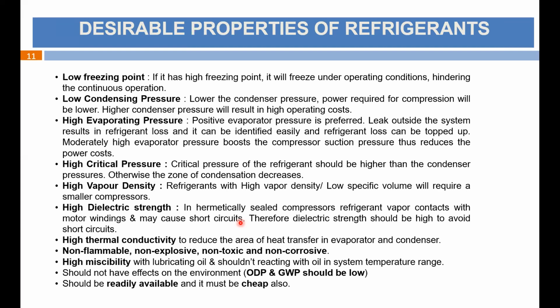And some refrigerants, as you know, operate at negative pressure, like R123. So positive evaporating pressure is preferred. If it is a negative pressure and any leak happens, then instead of refrigerant going out, the outside contaminated air gets in and the entire system gets contaminated. So there should be positive evaporating pressure. Moderately high evaporating pressure boosts the compressor suction pressure, thus reduces the power cost. And another thing is that high critical pressure.